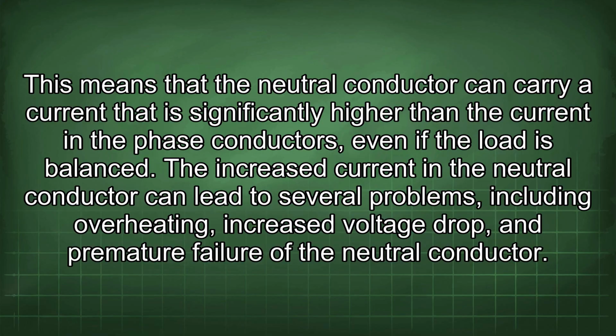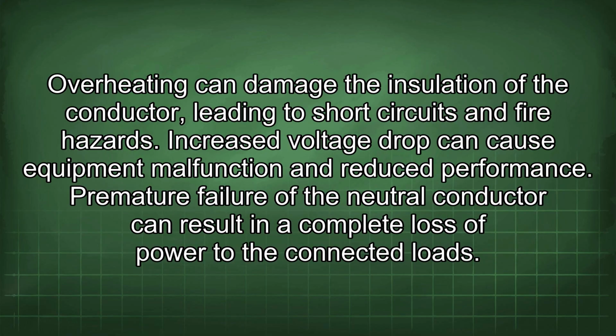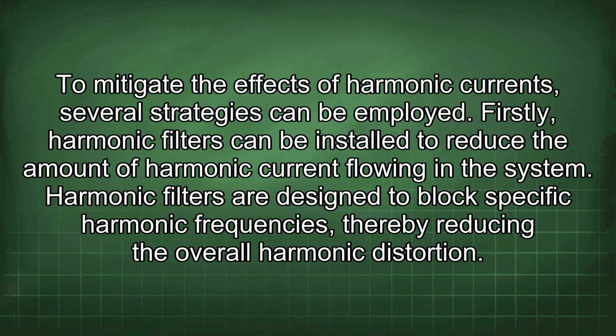The increased current in the neutral conductor can lead to several problems, including overheating, increased voltage drop, and premature failure of the neutral conductor. Overheating can damage the insulation of the conductor, leading to short circuits and fire hazards. Increased voltage drop can cause equipment malfunction and reduce performance. Premature failure of the neutral conductor can result in a complete loss of power to the connected loads. To mitigate the effects of harmonic currents, several strategies can be employed. Firstly, harmonic filters can be installed to reduce the amount of harmonic current flowing in the system. Harmonic filters are designed to block specific harmonic frequencies, thereby reducing the overall harmonic distortion.